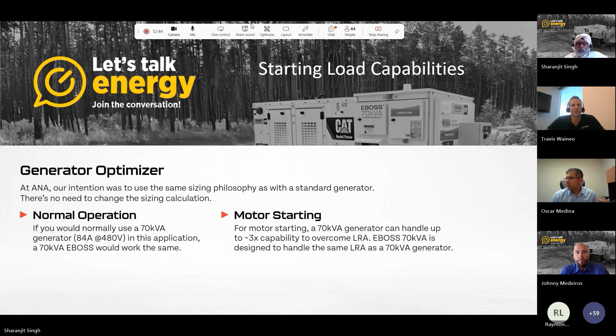A lot of battery systems might only rate their peak at 1.1, or 10% more than the continuous rating. We took that to the next level to match it to a generator. So we really oversized our inverters, the output. So then you wouldn't have to think through, okay, if I could start this thing with a generator, what battery size do I use? No, you just use the same rating battery size and it'll start the same piece of gear. Thank you very much, Travis.